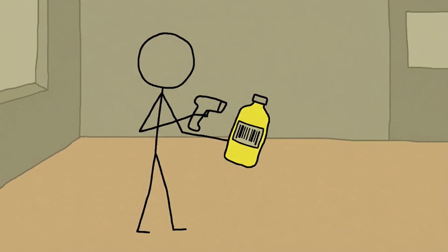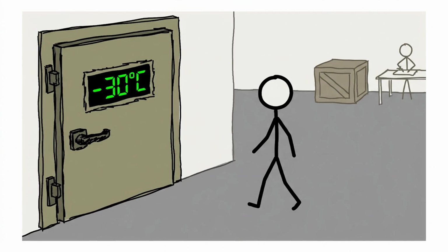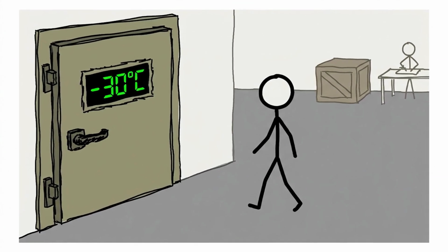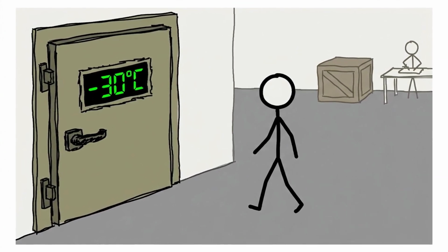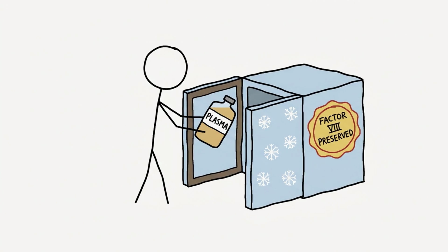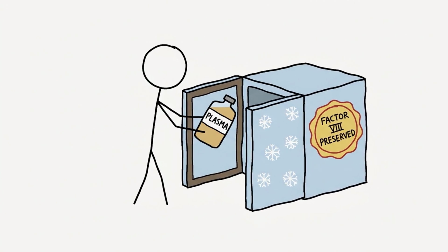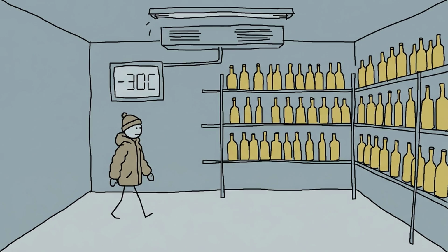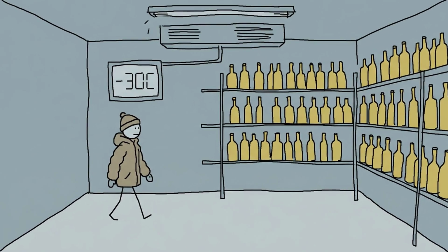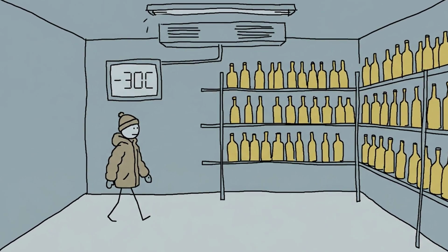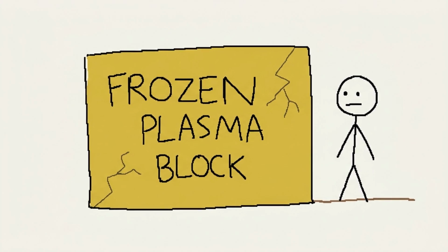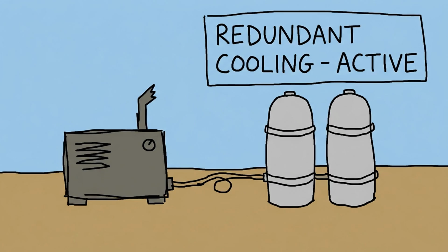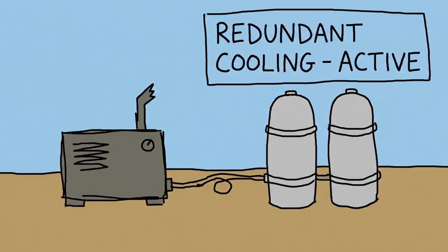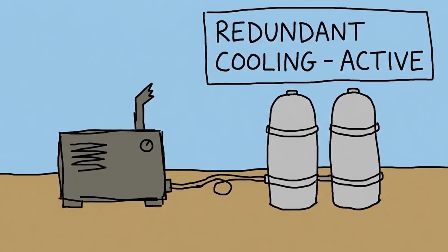Once collected, raw plasma bottles are barcoded and tracked through centralized software systems before entering specialized blast freezers within 6 hours. Immediate blast freezing is essential to preserve heat-labile clotting factors like factor VIII. Industrial blast freezers drop internal cabinet temperatures to minus 30 degrees Celsius or colder, instantly freezing liquid plasma into solid amber blocks. Secondary redundant liquid nitrogen cooling loops ensure zero temperature drift during power outages.